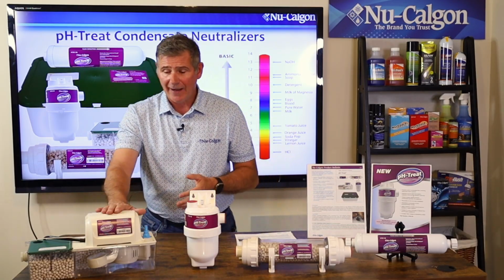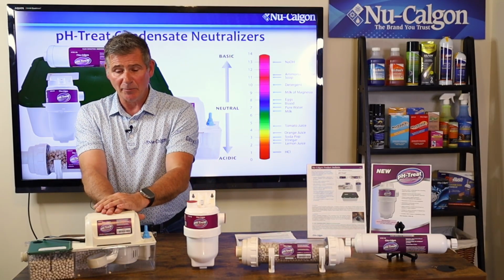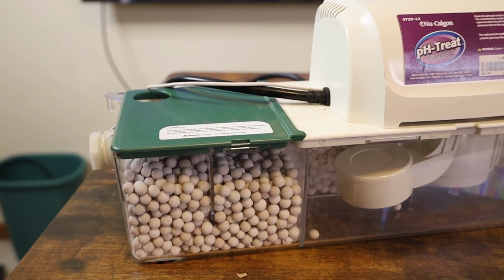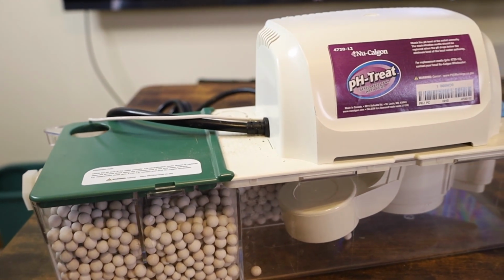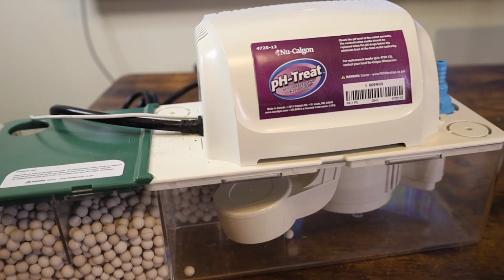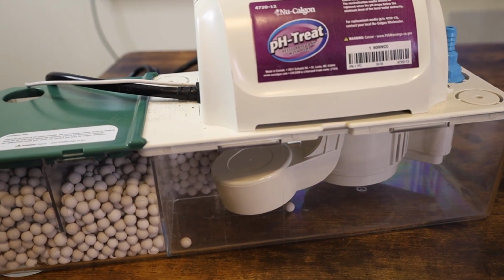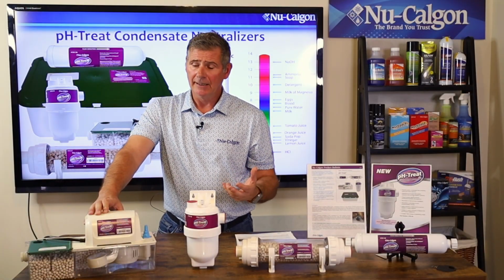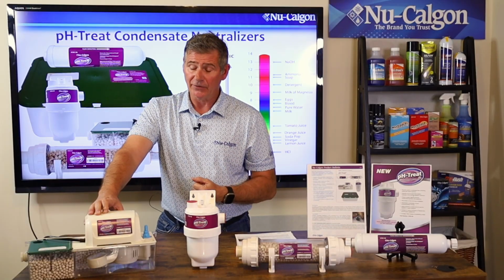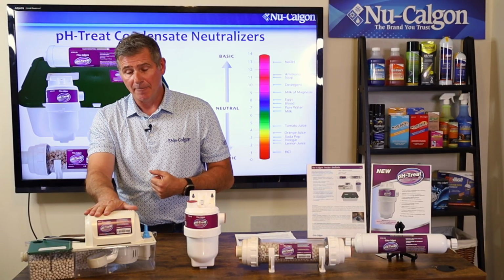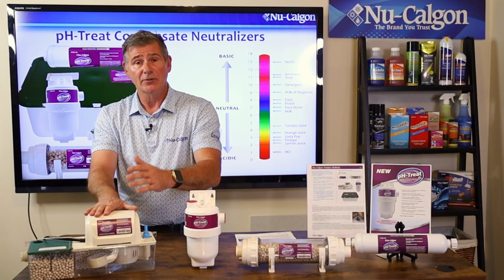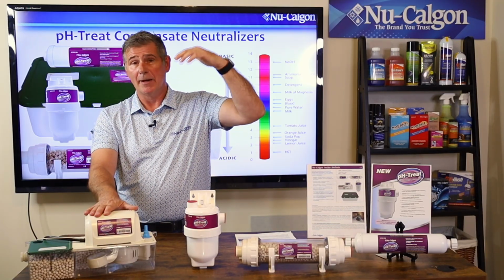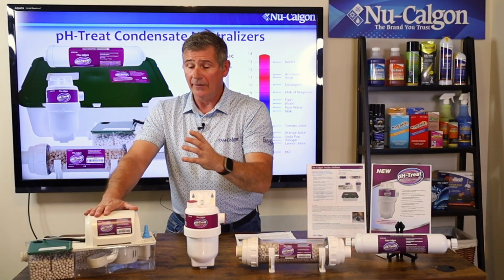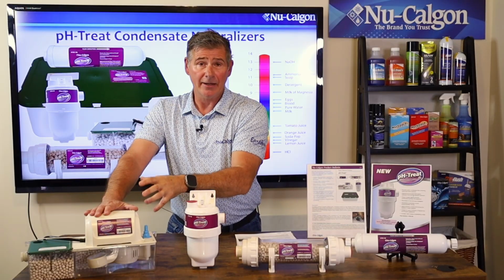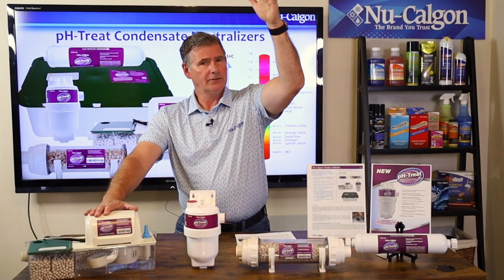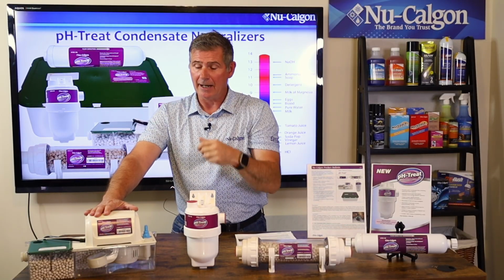And then finally, this is a really unique one because, well, it's a condensate pump. So what's really nice about this is this will do up to a 500,000 BTU system, or about 1.9 gallons per hour worth of condensate flow. But being a condensate pump, this can be put into a basement. So if you have to pump condensate water up out of a basement or a crawl space, this is going to provide you about 20 foot of head or 20 foot of lift. So it's got a really nice pump in it, so it can get it up out of a basement or a crawl space.